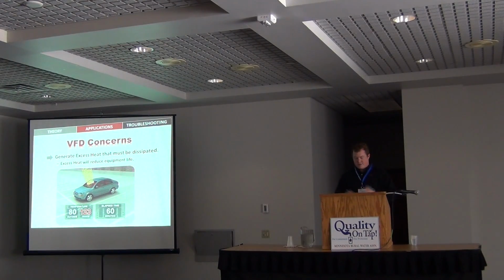Concerns. So those are all the benefits. Now we're going to roll into some of the concerns of using a VFD, to make sure you don't run into issues. VFDs, because we're converting from AC to DC back to AC, there's heat losses in all these processes, and because we have that high switching speed, there's heat losses there, and we need to do something with that heat.